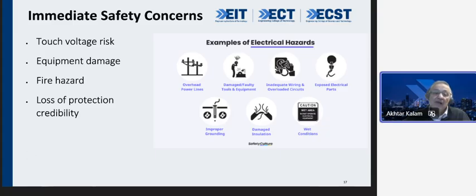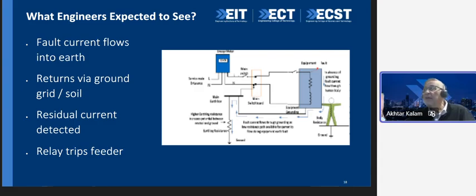Now, all of you who have done an undergraduate qualification in engineering know what you want to see. And as I told you, I already have a mental model of my system, and we all have that. It's going to bring misunderstanding to whatever we are doing. We are expecting to see fault current flowing through the earth. This is what we are expecting. Return is via the ground grid or soil. We expect that there will be a residual current and we can detect it. We expect that the relay will trip.